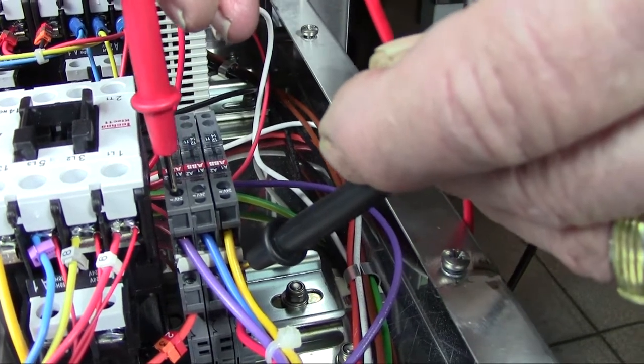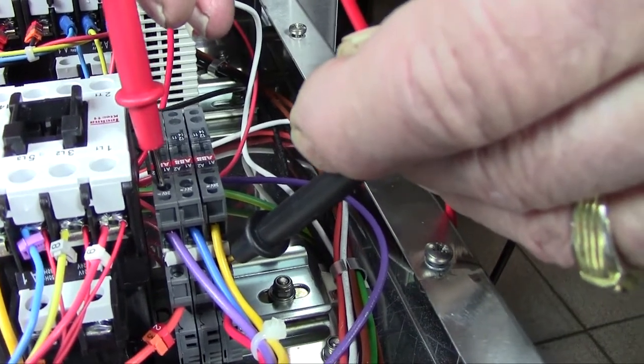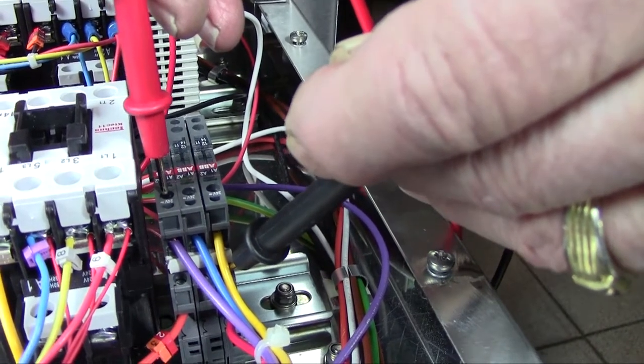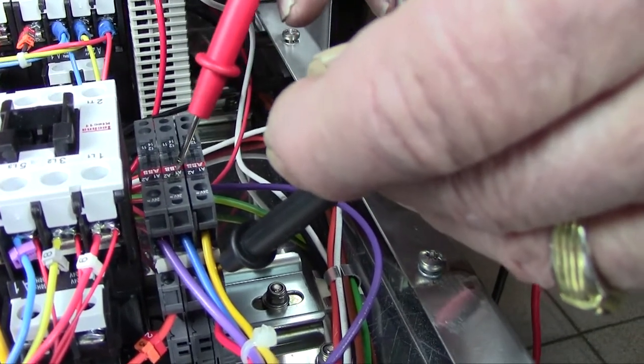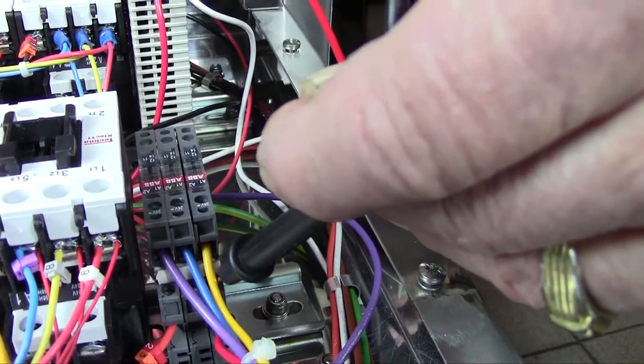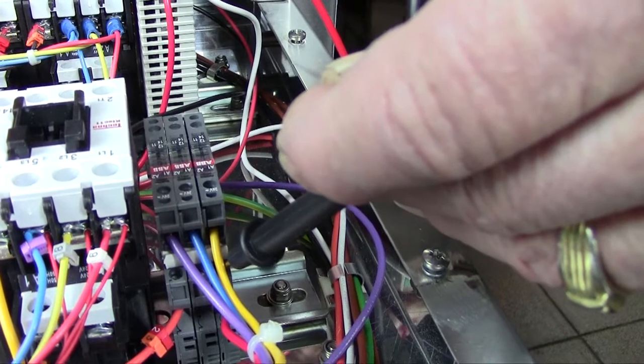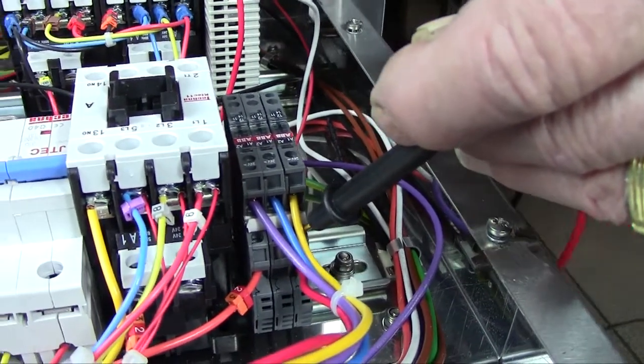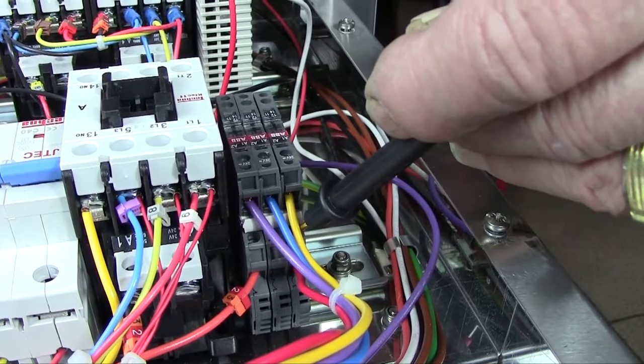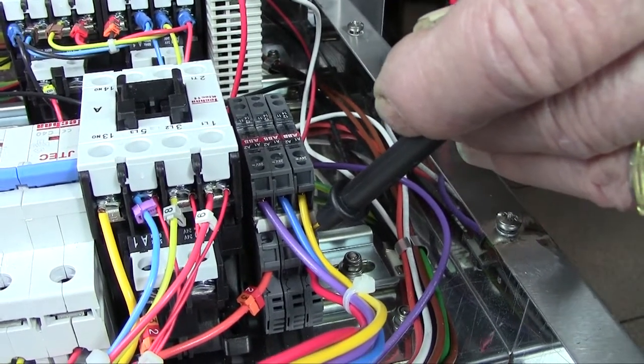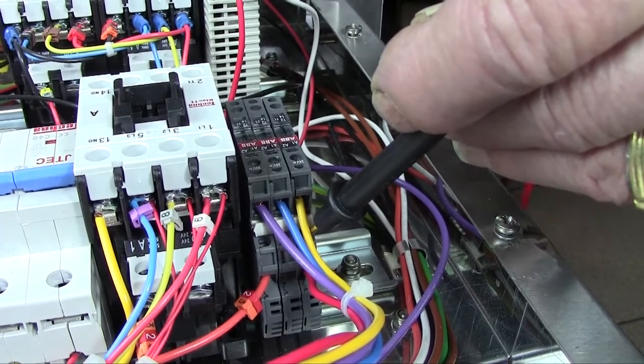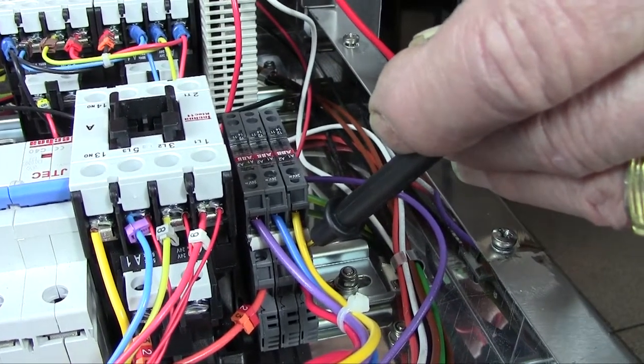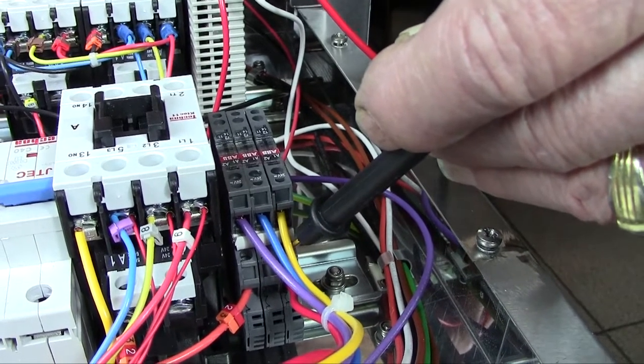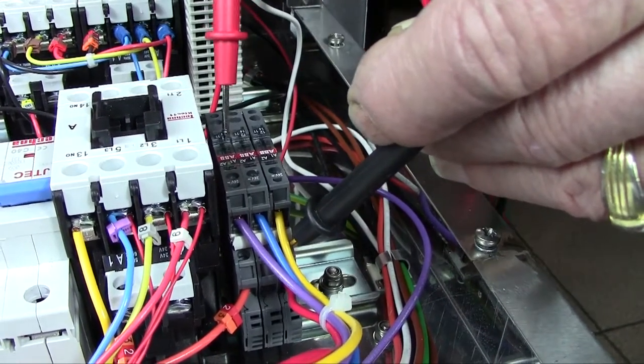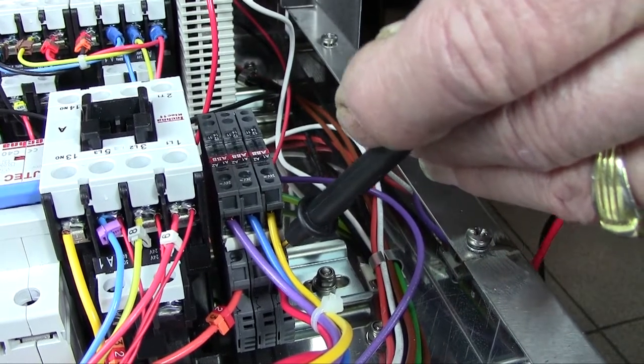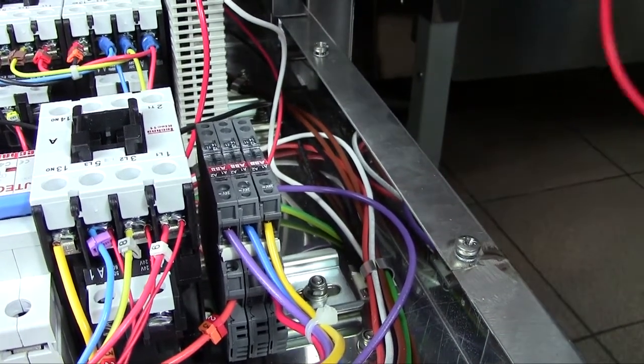Wait for the green light to come on the relay so that you know that the current is there to check that it's correct. When that relay is working as it is now, the green light will light and the contactor appropriate to it will pull in. That means both coils are working on the relay and the contactor. And it applies to the top and the bottom the same. Now, as you've just heard, the bottom contactor has gone in and the bottom relay was alight. So we know that the coils are working on both of those.